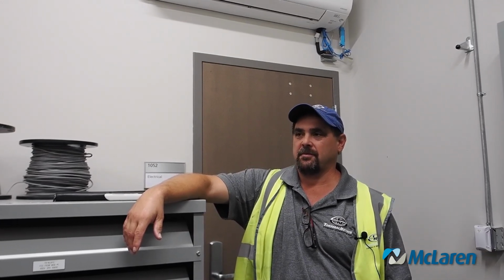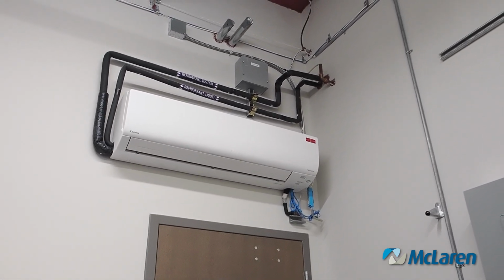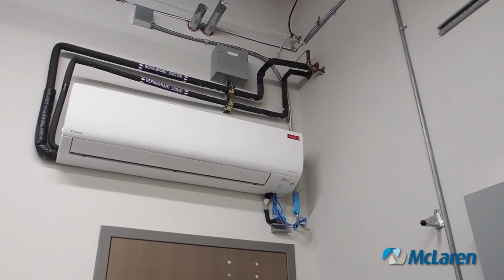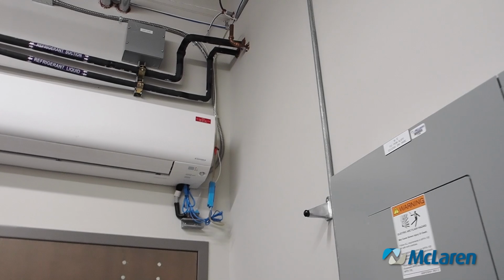The only reason I ask is because the school didn't realize they should clean them, because in the summer months when the kids are not at school, they're not using them. So then when they go to kick them back in, that little pump, if it isn't cleaned out, it'll clog up. And the reality is people don't really clean it as often as they should. They'll change or clean the filter more than they will clean that pump. So that's when I mentioned at the time to flush it out.